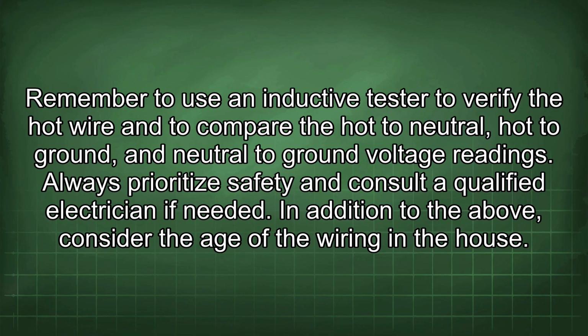Remember to use an inductive tester to verify the hot wire and to compare the hot to neutral, hot to ground, and neutral to ground voltage readings. Always prioritize safety and consult a qualified electrician if needed. In addition to the above, consider the age of the wiring in the house.